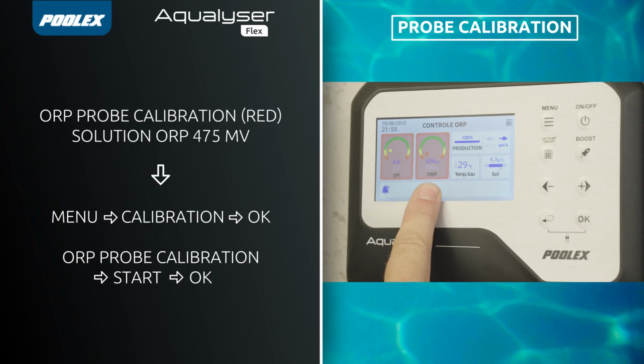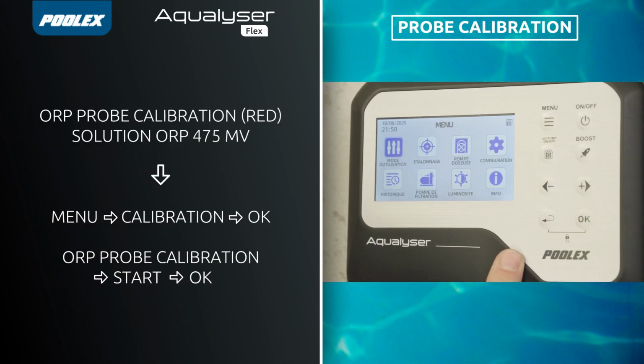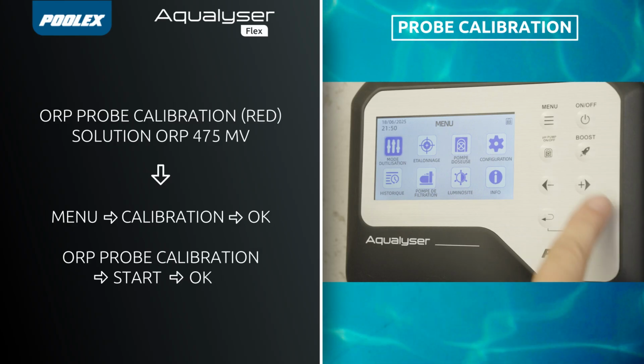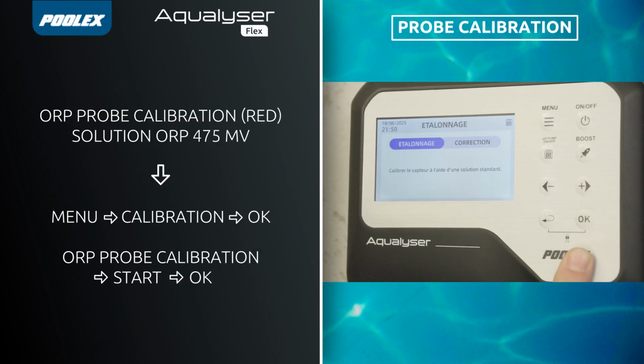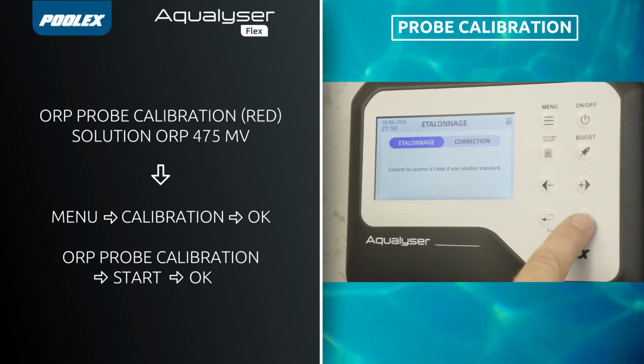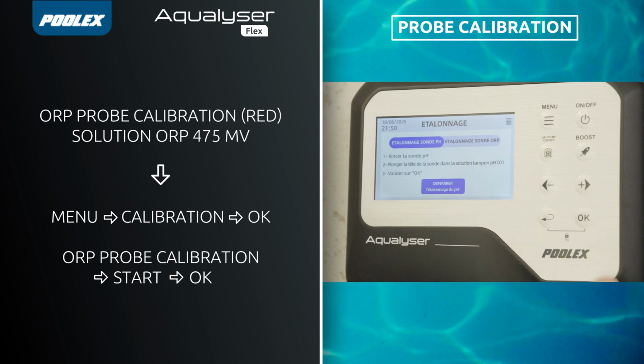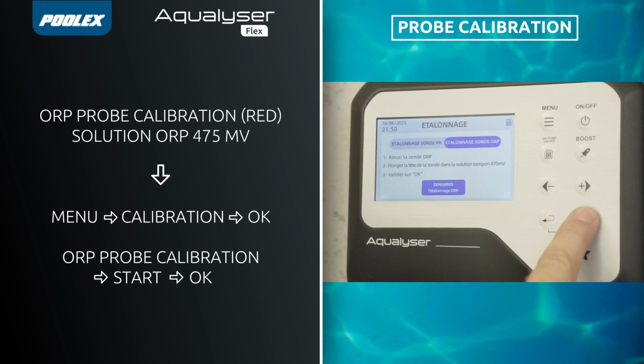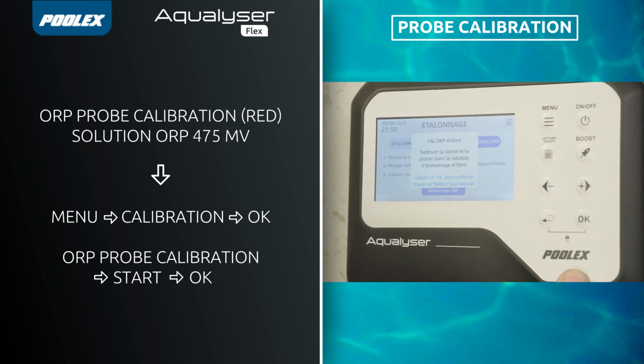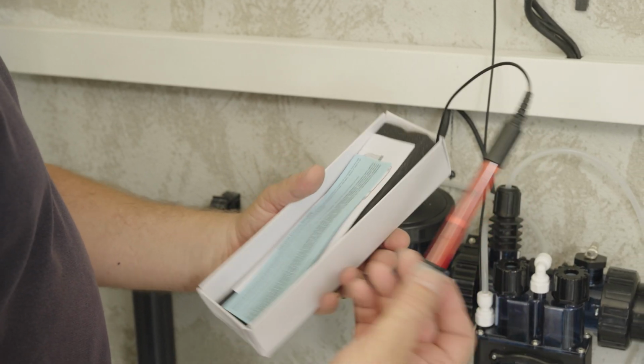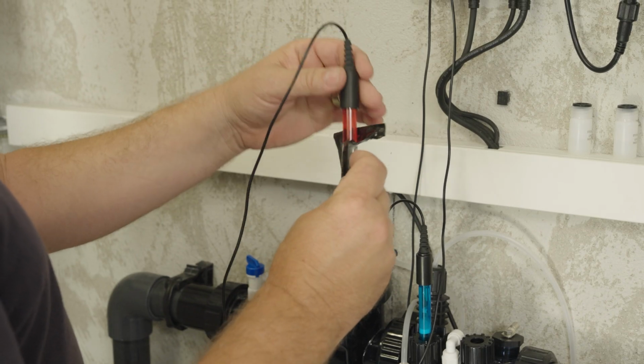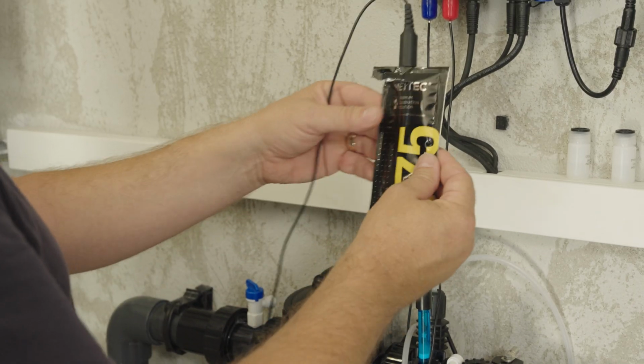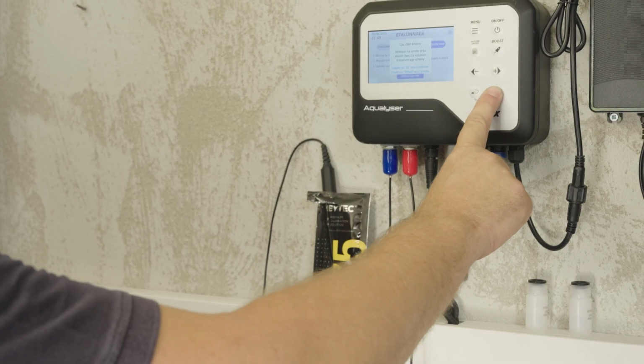To calibrate the ORP probe, in the menu, use the arrow keys to select Calibration, then confirm with OK. Choose Calibrate ORP probe. Press Start Calibration. A message will guide you to finalize the procedure. Remove the probe from its holder and immerse it in the ORP 475 mV buffer solution and press OK.